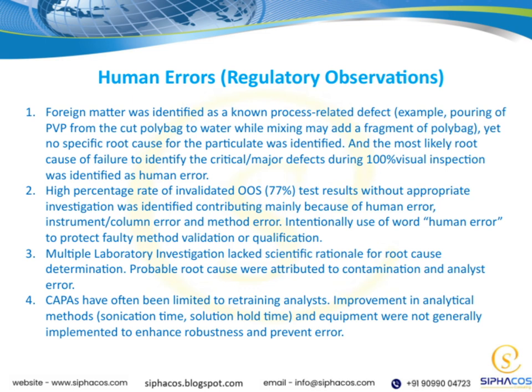While contamination and analyst error were frequently suggested as probable causes, these conclusions were sometimes made without thorough scientific backing. Furthermore, CAPAs, or corrective and preventive actions, were often limited to retraining analysts. There was little evidence of systematic improvements to analytical methods, such as adjusting sonication times or solution hold times, or upgrades to equipment to enhance overall robustness and prevent errors from happening again.